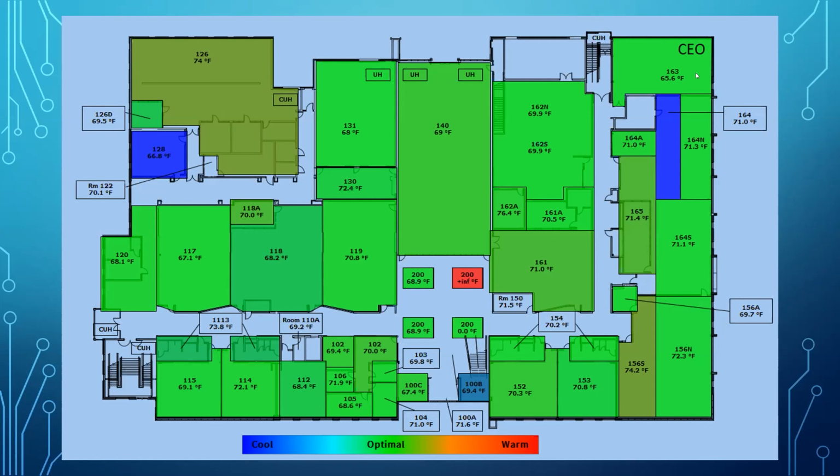So we do apparently have a graphical issue here, which brings us to one of the challenges that we run into with a lot of building systems: they're built by people. People make mistakes. So apparently we have an issue where we have mislinked our graphic here. Maybe this isn't actually representative of our space.